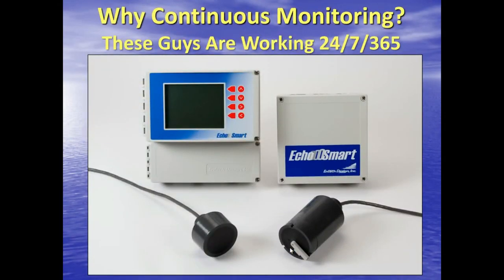There are two main products: the EchoSmart, usually used for measuring sludge, and the FilterSmart for use in a gravity filter. They both use the same hardware — the difference is in the software. The device with the display is what we call our controller; it is not the analyzer, because the analyzers are down in the sensors. You've got the EchoSmart controller, a power supply that's really a communications hub, and three different sensors: a standard sensor, a self-cleaning wiper sensor, and the FilterSmart sensor which has a built-in turbidimeter.